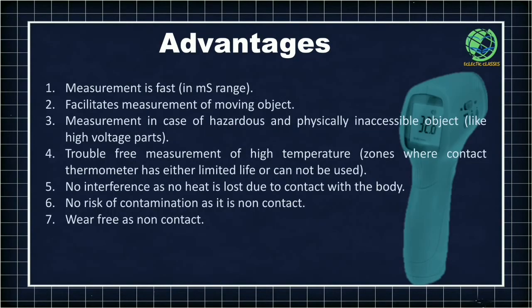Now, what are the advantages of infrared thermometers? Infrared thermometers are really fast — they can measure temperature in milliseconds, while RTDs or thermocouples can measure temperature in multiples of seconds only. They can also be used to measure the temperature of moving objects. In case of hazardous or physically inaccessible areas like high voltage parts, infrared thermometers are quite useful. In very high temperature zones where contact thermometers have very limited life or cannot be used at all, infrared thermometers are also very helpful.